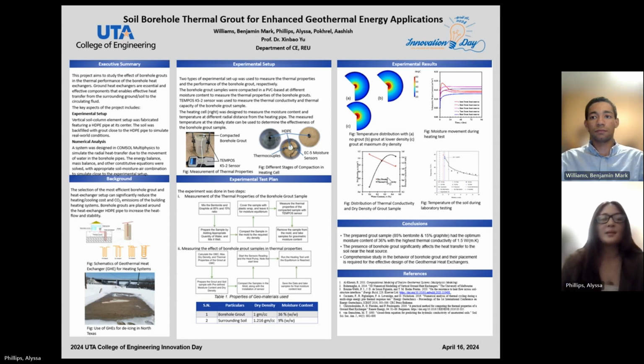Thank you, Ben. Our experiment was done in two steps: measurement of the thermal properties of the borehole grout sample, and measuring the effect of the borehole grout samples on thermal properties. For the first step, we conducted a standard Proctor test on a mix of 85% bentonite and 15% graphite to find the optimum moisture content, which gave us the highest thermal conductivity.